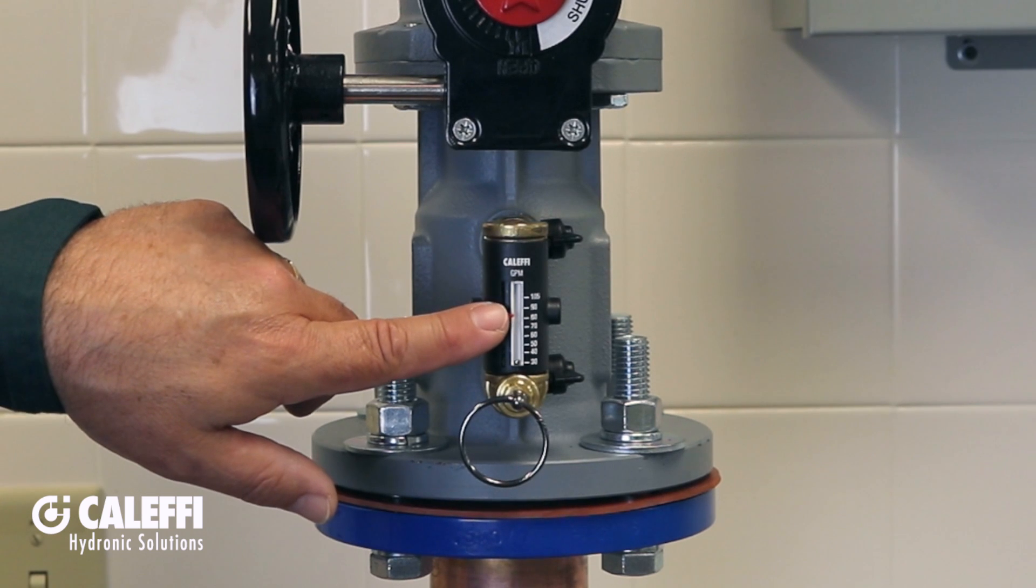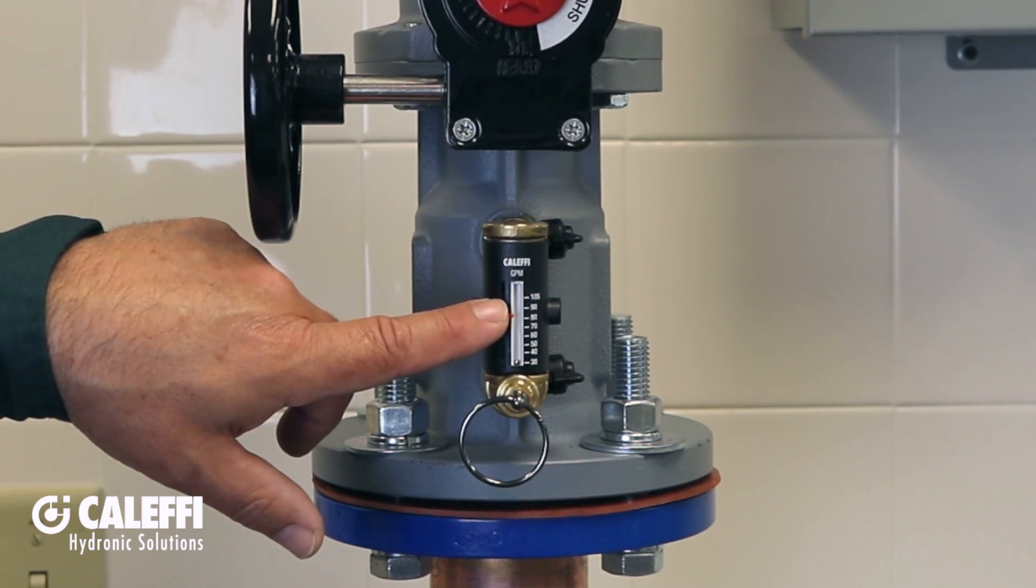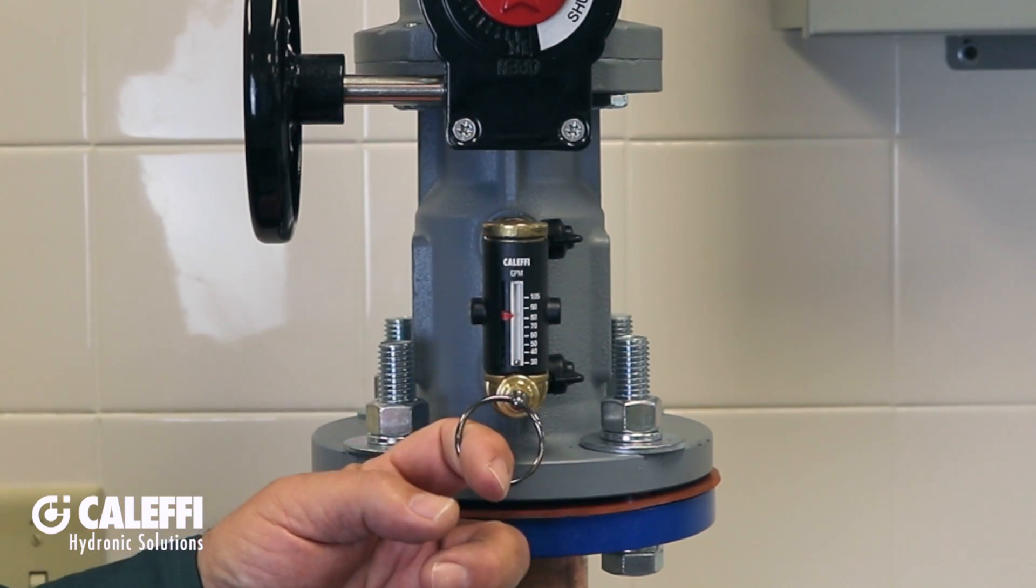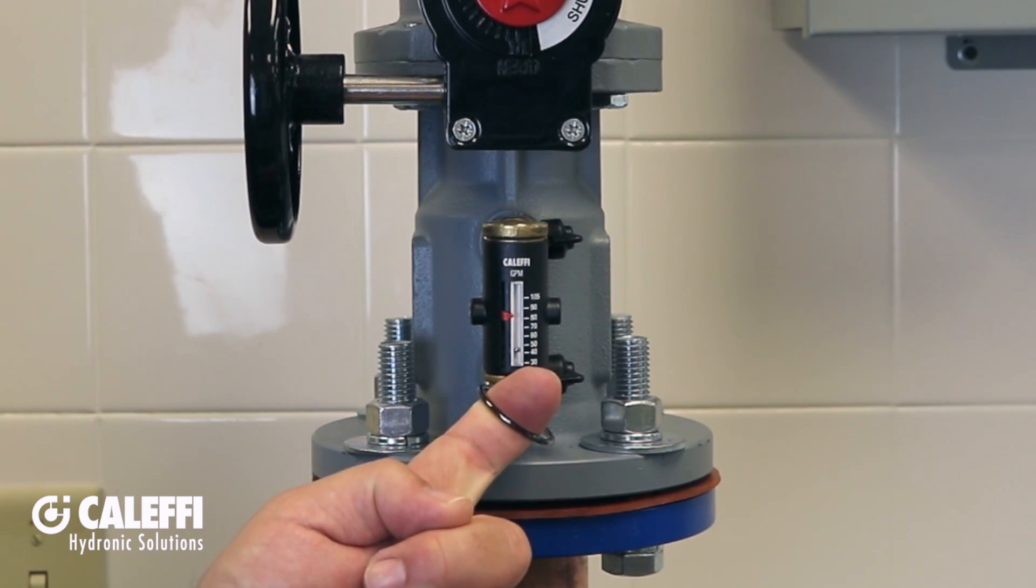This little red sliding design flow rate pointer allows you to set your design flow rate on the scale. To read the flow when you're balancing or at any other time that you want to check the flow rate, simply pull this ring when the system pumps are running.